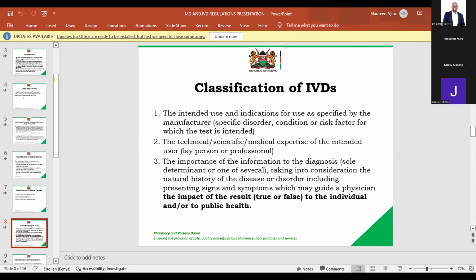For the IVDs, we look at these three factors. Of course, we have to look at the intended use and the indication. We also need to see the technical, scientific, or medical expertise of the intended user. Here we talk about the lay person or the professional, because we find that there are some in vitro diagnostics that are used by the lay person, people who have no scientific or medical expertise. So there are some factors to consider during evaluation of this IVD. Something like instructions for use, which have to be very detailed, very simple and able to be followed.